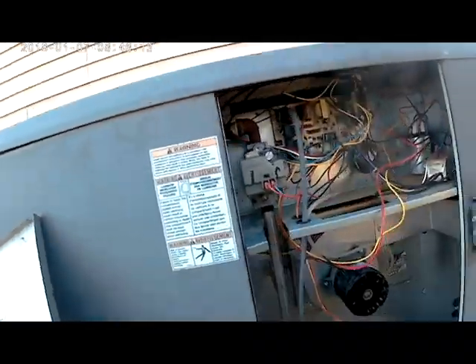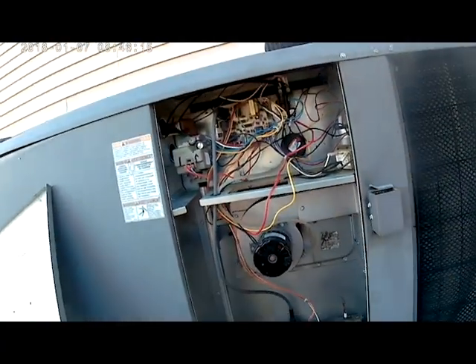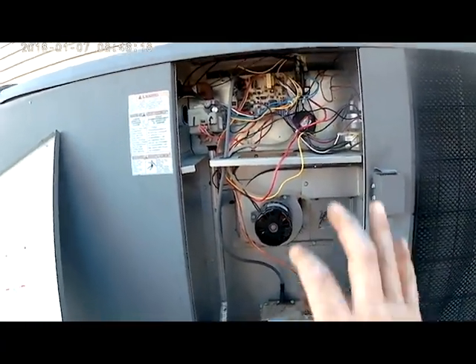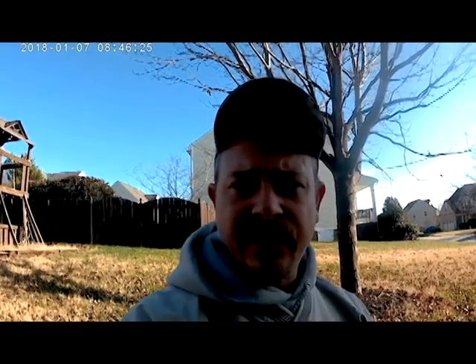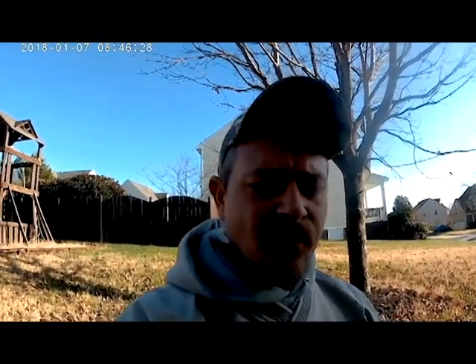But this heat exchanger is pretty easy, it's just a point of finding all the screws you need to take out and put back in. Once you take it out, you basically do that process in reverse, and you know where everything goes. Pretty easy heat exchanger. Like I say, we had to remove the control panel, all of it, remove the top, and the heat exchanger just slid out and slid back in. But this is a good one to see, especially on these gas packs, the tubular style heat exchangers, how they rust out and where you get the rust holes. This one was rusted pretty bad in pretty much each one of the cells.